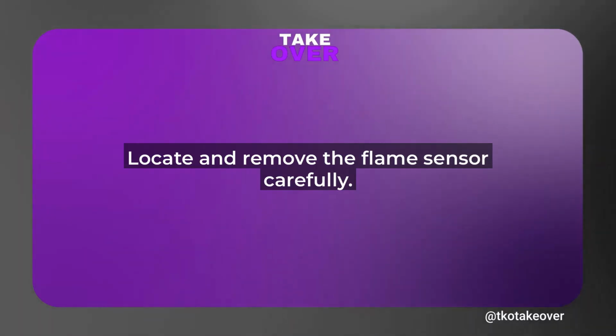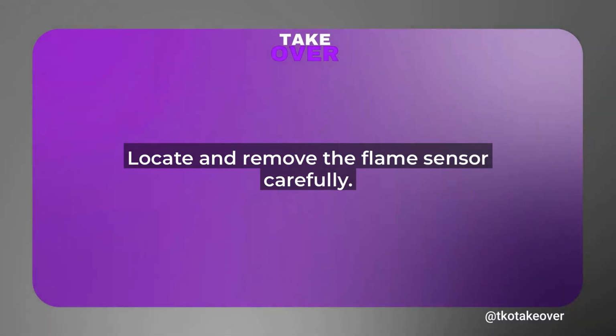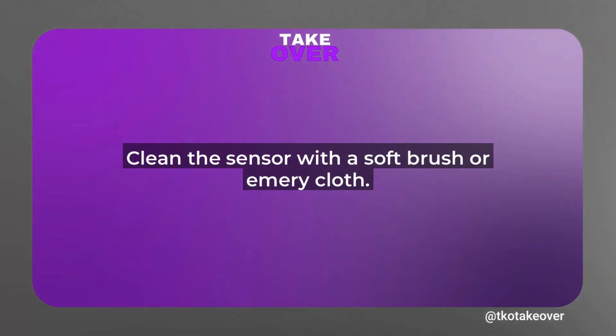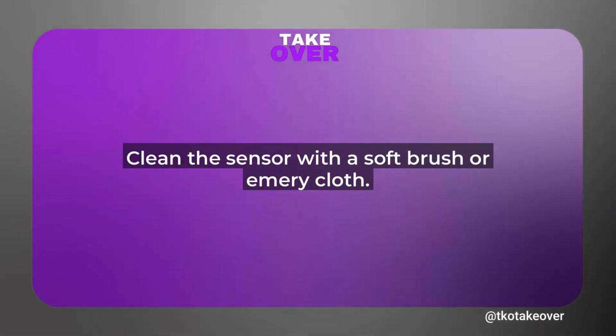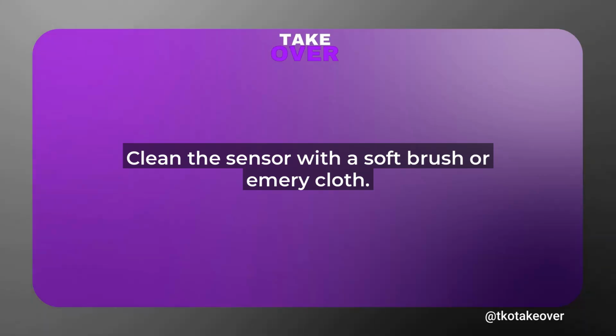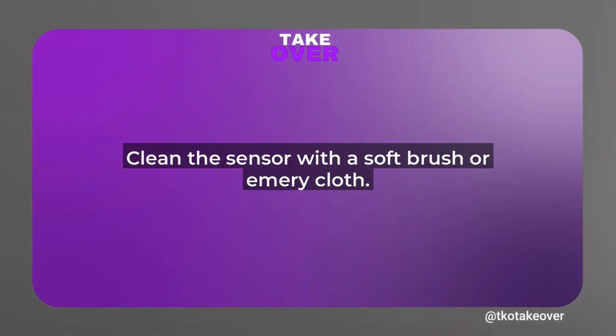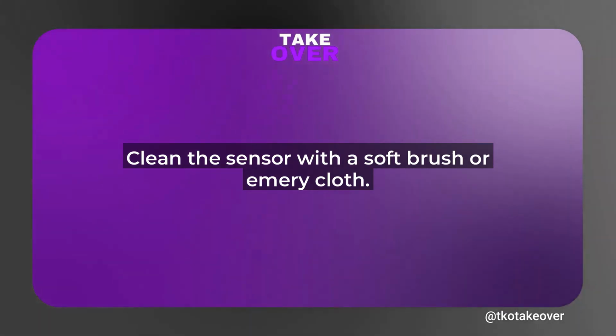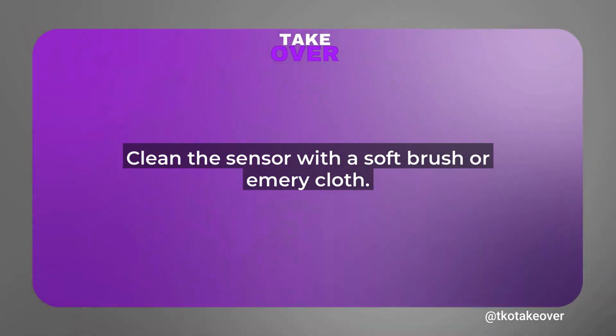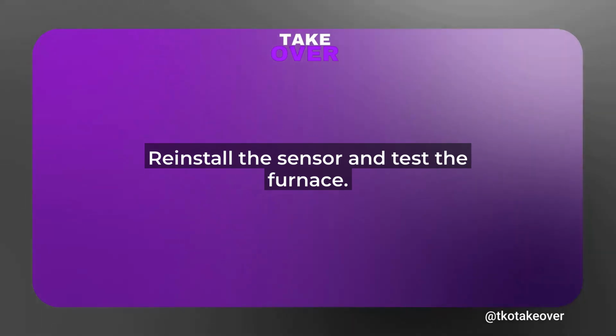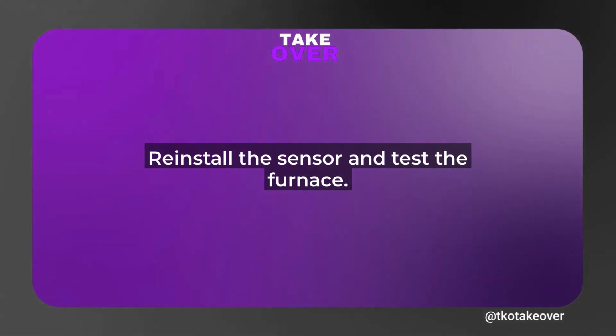Now, let's get to the root of the problem. Error code 58 usually means the furnace isn't detecting a flame properly. Start by locating the flame sensor, a small metal rod near the burner assembly. Carefully remove it by unscrewing it from its position. Use a fine emery cloth or a soft brush to gently clean off any soot or buildup. This is a common culprit, and a quick clean might resolve the issue.